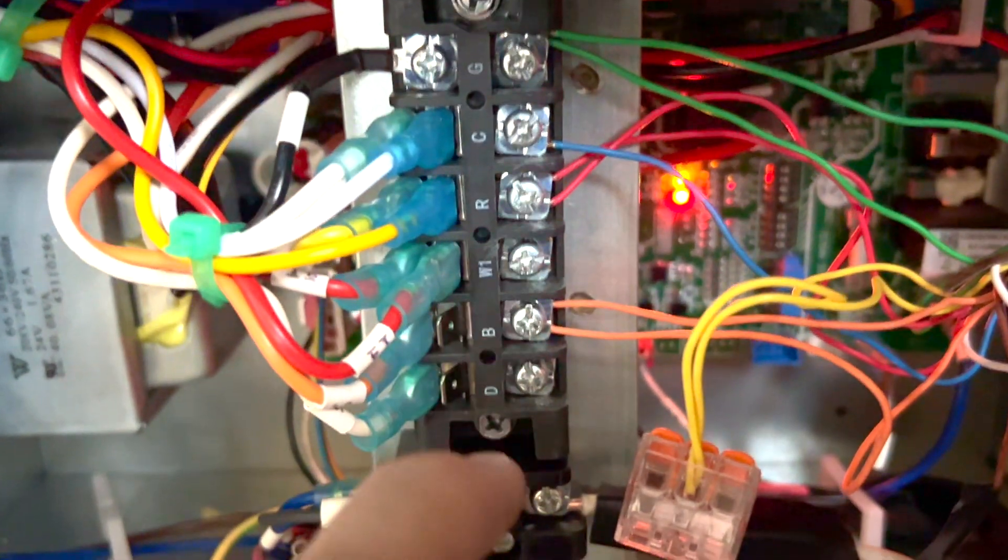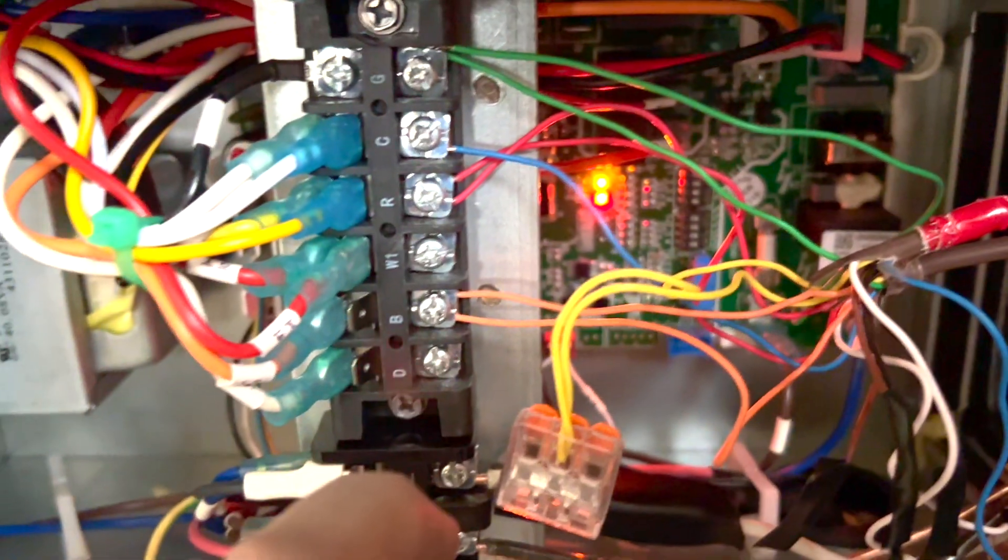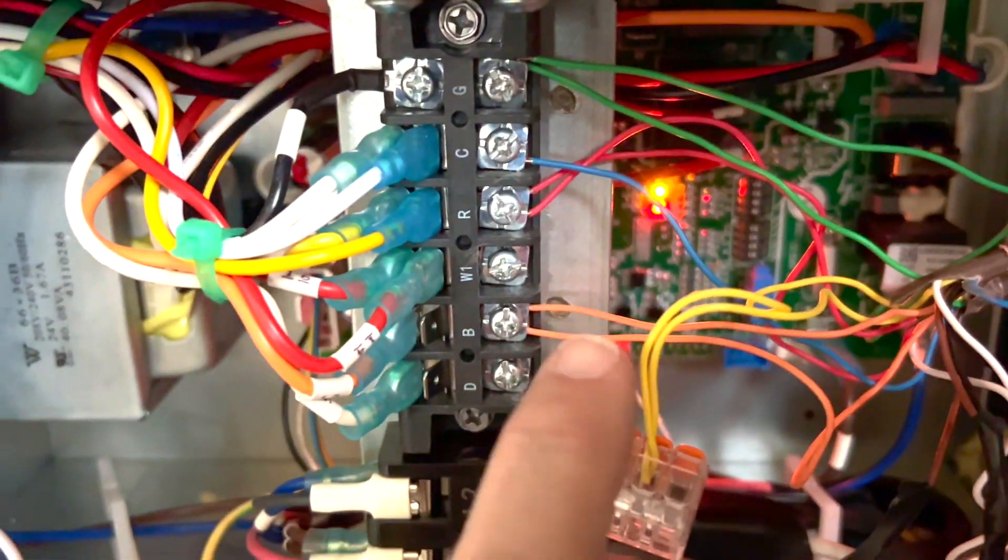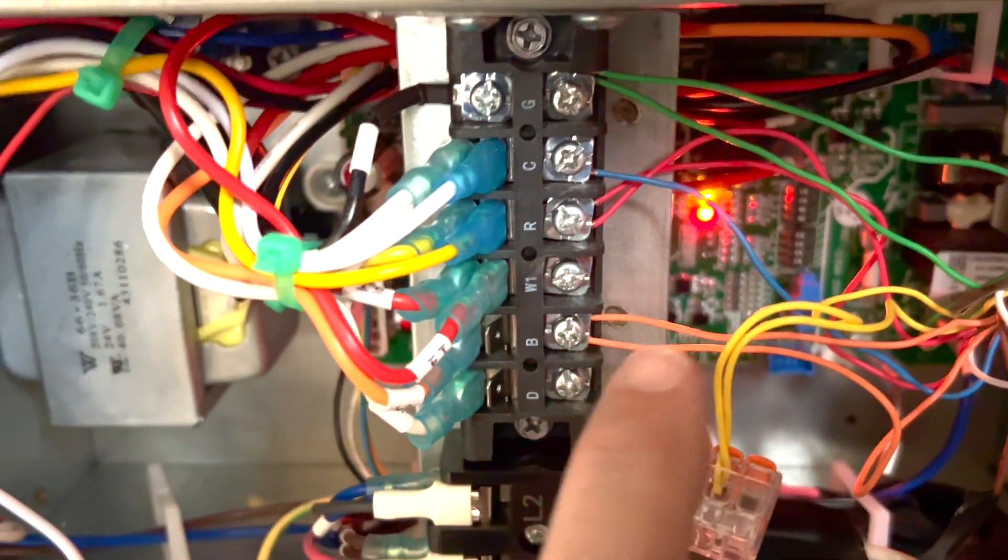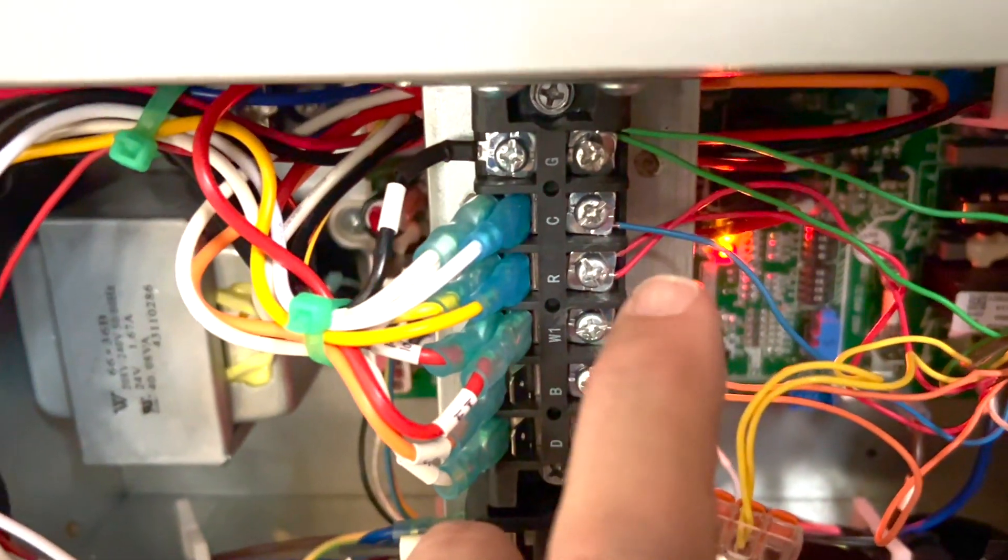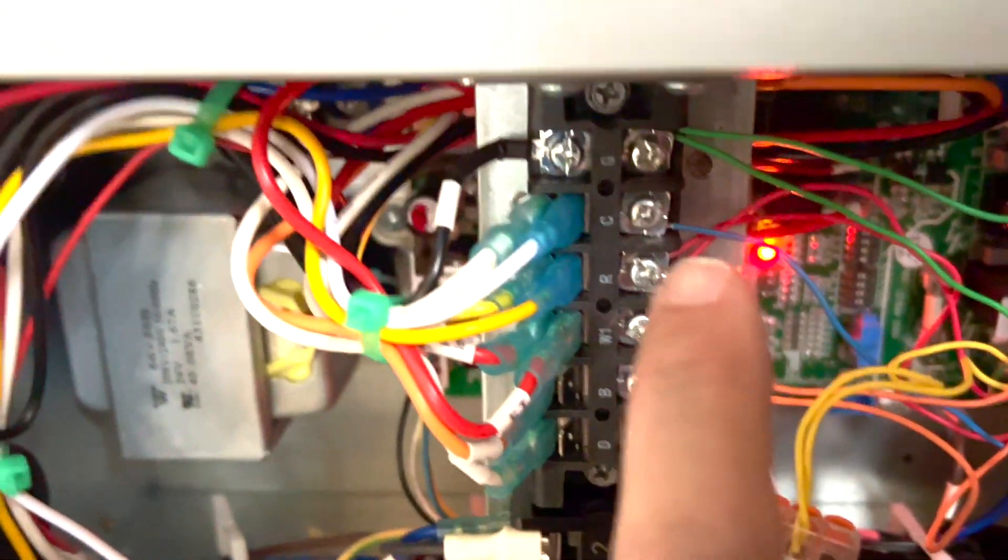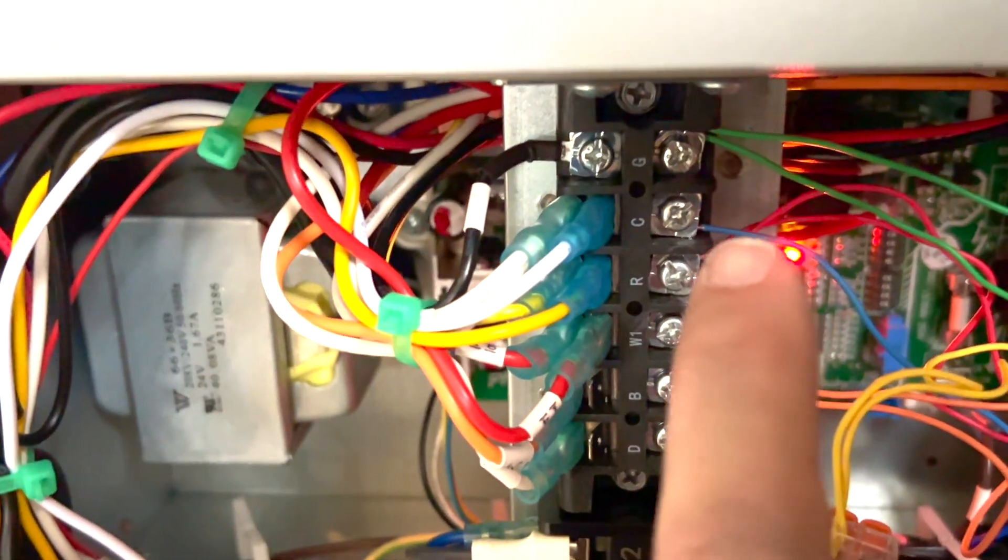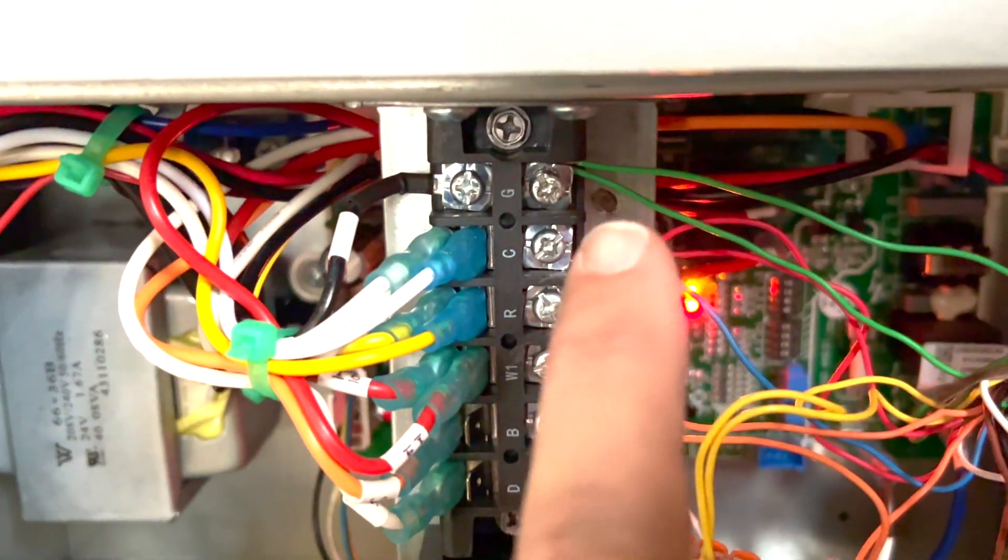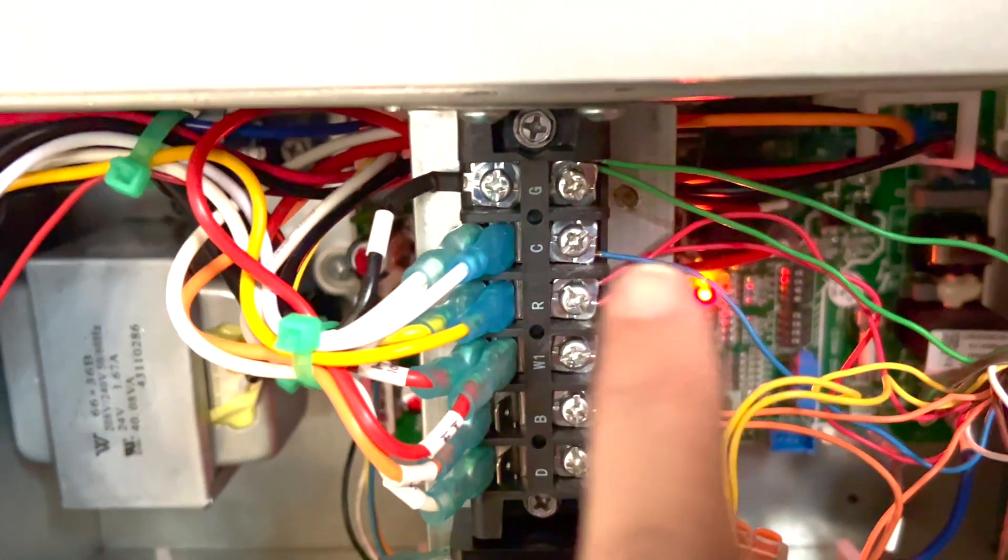Here's the air handler setup. We have double wires going from thermostat to here to condenser—double orange for B, double red for your power, a single blue common going to the condenser, and double green going from thermostat to here to condenser.